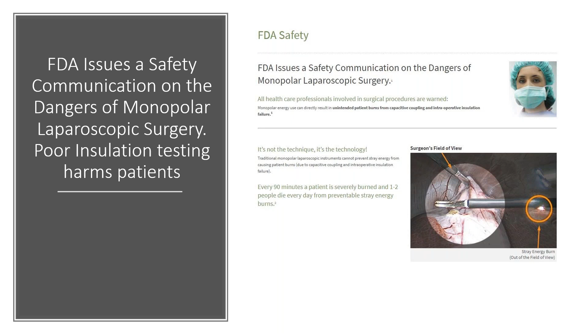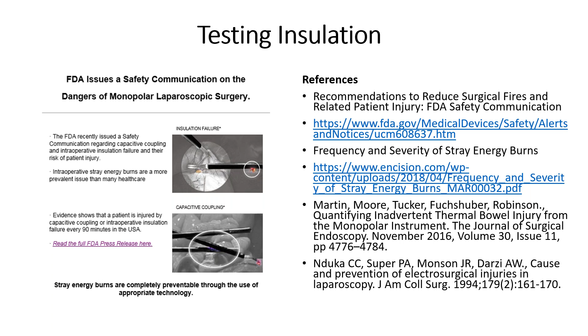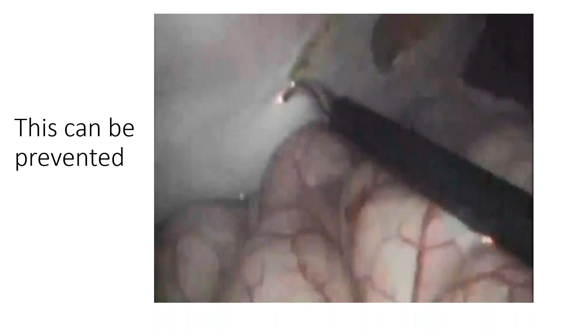For example, minimally invasive surgical instruments are growing rapidly. And this one is interesting: the FDA put out this safety communication on the danger of monopolar laparoscopic surgery, that poor insulation causes harm. It said every 90 minutes a patient is severely burned, and 1 to 2 people die every day from preventable stray energy burns. I will show you a little video clip coming up, but it is really important. If you want to look at the full FDA release, you can go on the FDA website and see the issue. But here's one example, and I will repeat this. Look at this area on the right. This was caught on camera, basically.